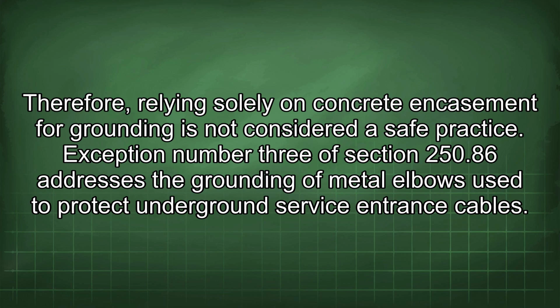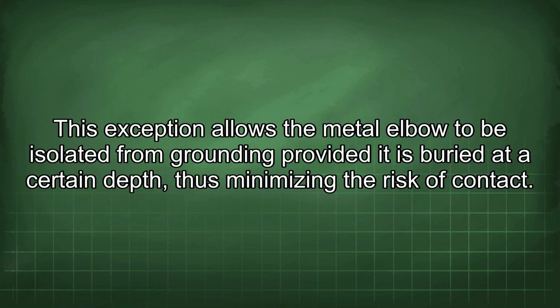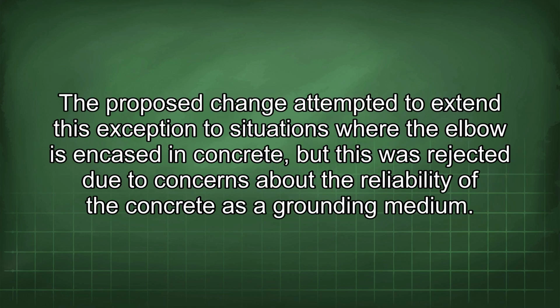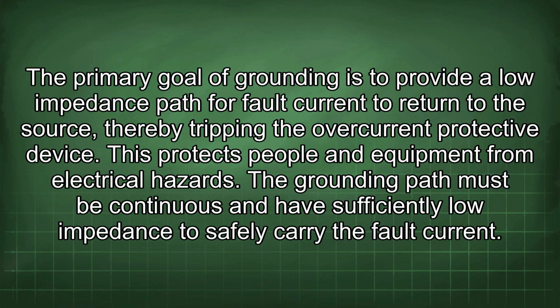Exception number 3 of section 250.86 addresses the grounding of metal elbows used to protect underground service entrance cables. This exception allows the metal elbow to be isolated from grounding provided it is buried at a certain depth, thus minimizing the risk of contact. The proposed change attempted to extend this exception to situations where the elbow is encased in concrete, but this was rejected due to concerns about the reliability of the concrete as a grounding medium. The primary goal of grounding is to provide a low impedance path for fault current to return to the source, thereby tripping the overcurrent protective device. This protects people and equipment from electrical hazards.